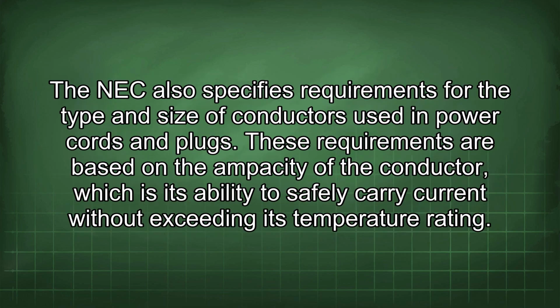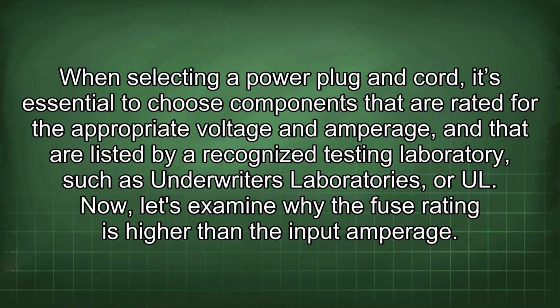hazards. The NEC also specifies requirements for the type and size of conductors used in power cords and plugs. These requirements are based on the ampacity of the conductor, which is its ability to safely carry current without exceeding its temperature rating. When selecting a power plug and cord, it's essential to choose components that are rated for the appropriate voltage and amperage, and that are listed by a recognized testing laboratory, such as Underwriters Laboratories, or UL. Now let's examine why the fuse rating is higher than the input amperage.